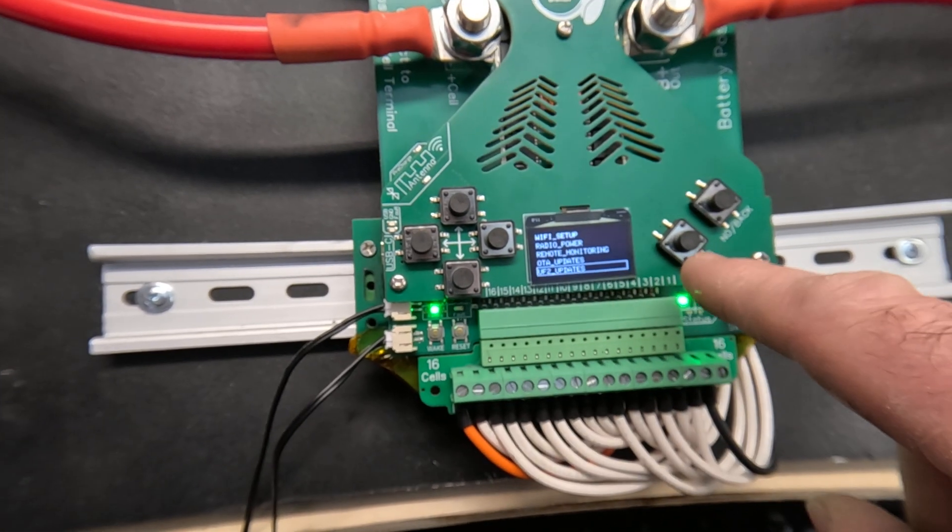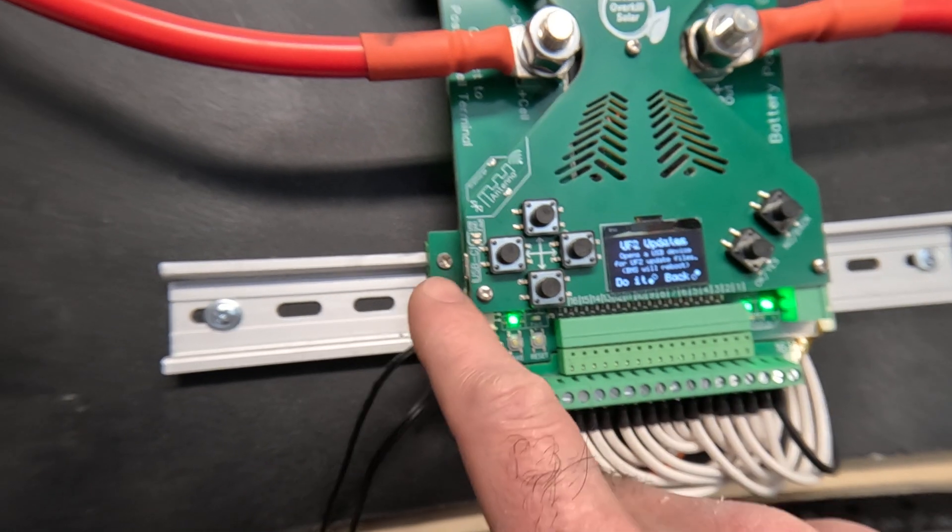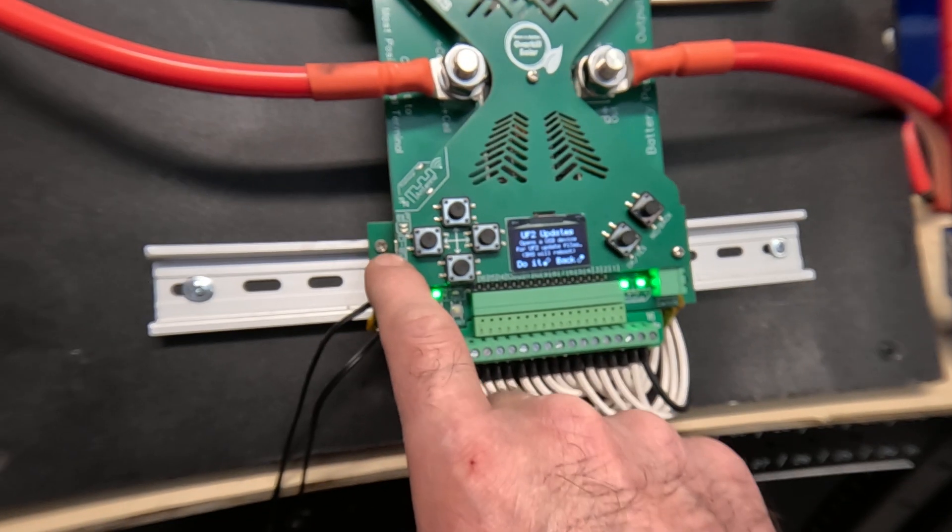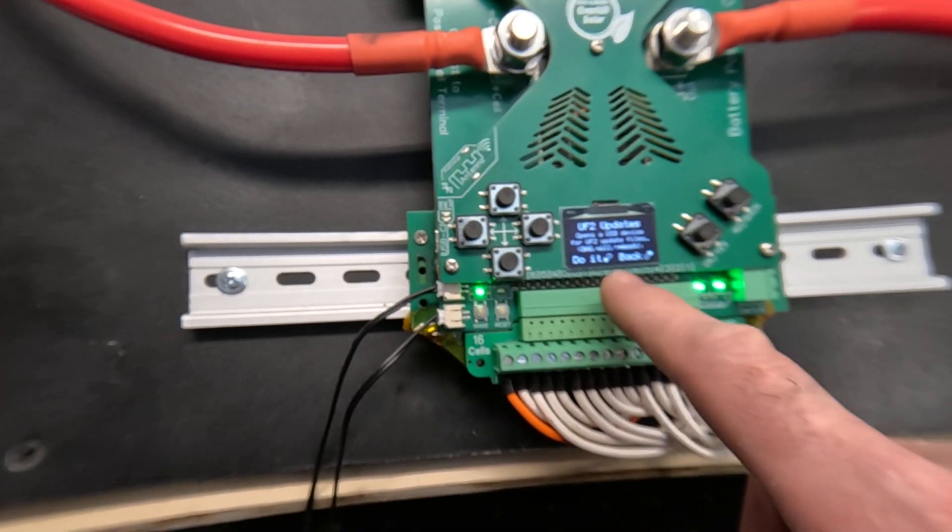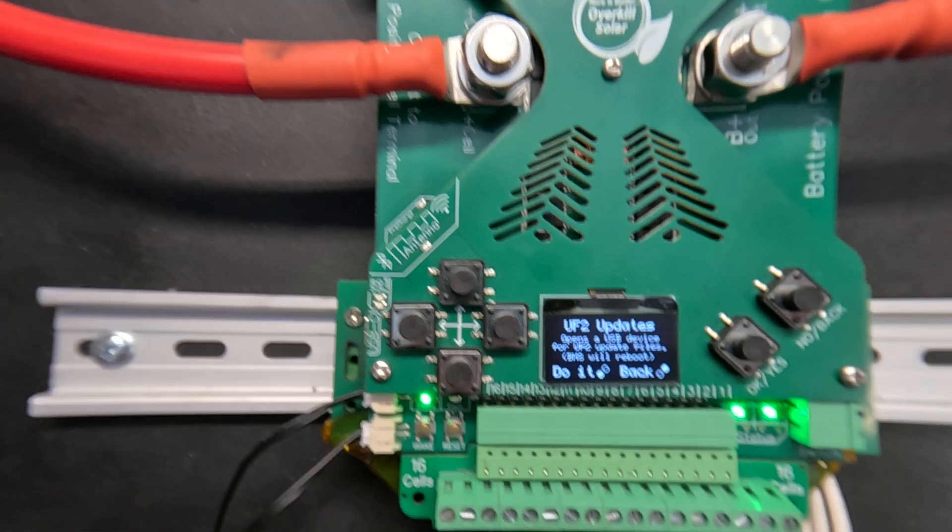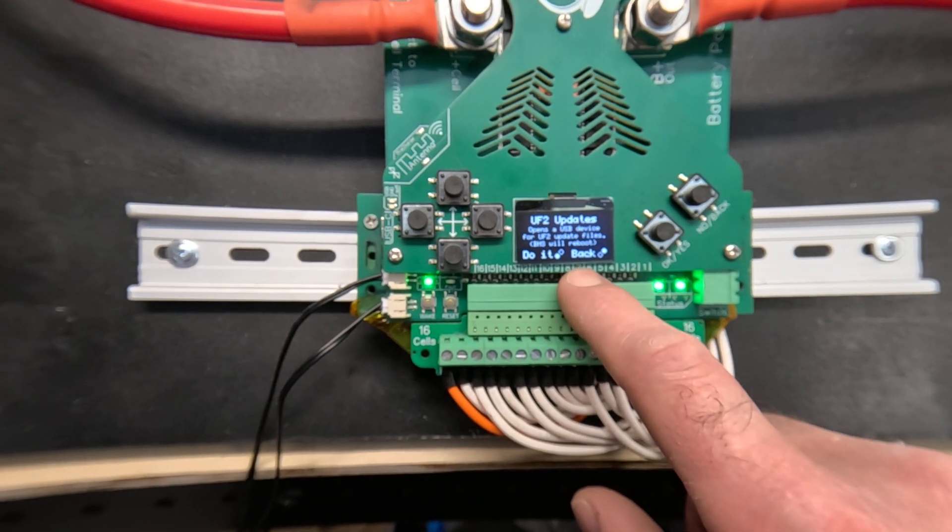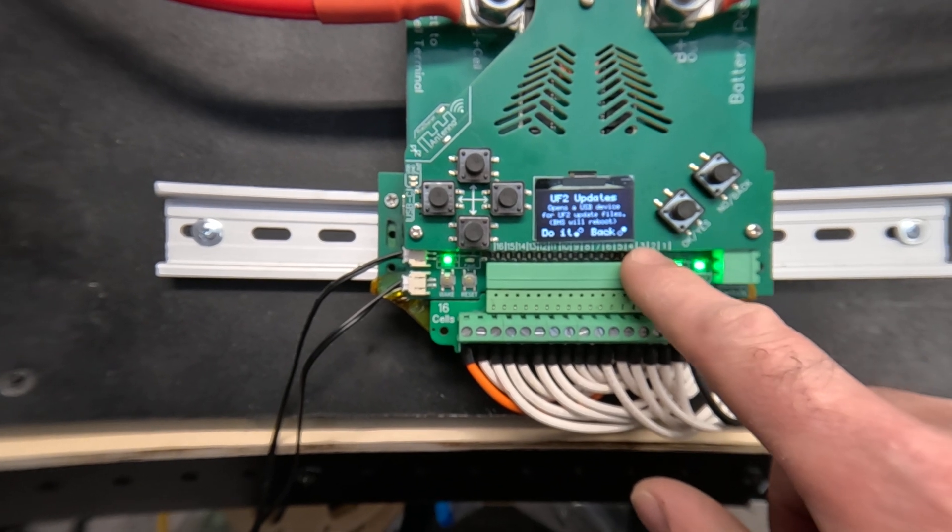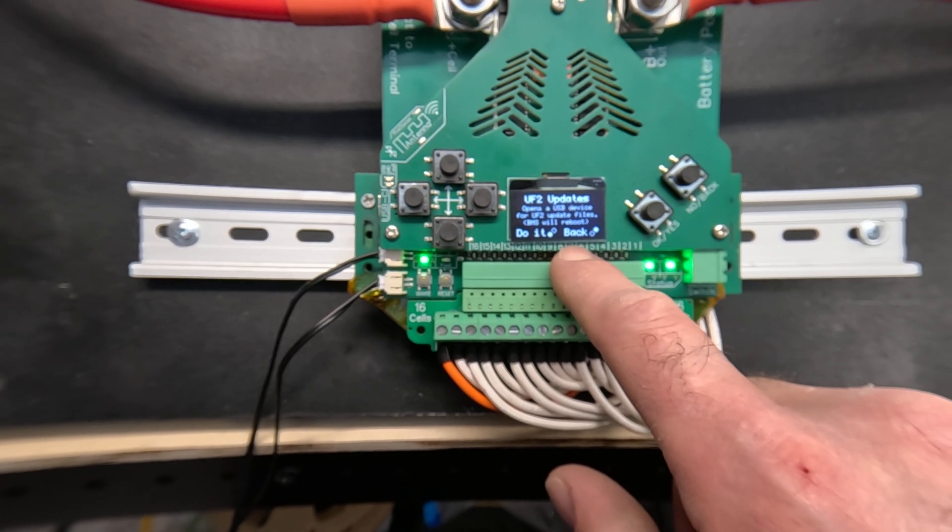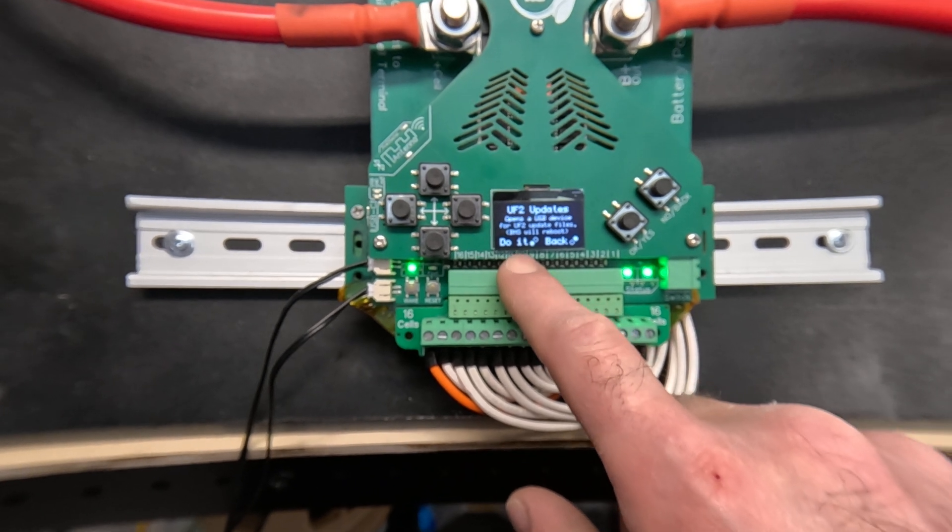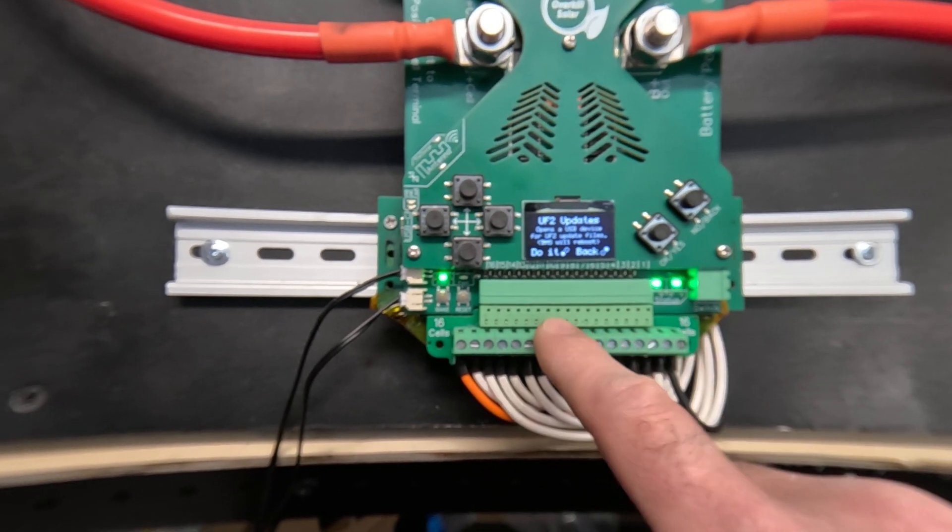You can also enter the UF2 update mode. This is how you update via the USB. So you would connect this to your PC and download the UF2 format firmware or update. And then you just drag and drop it into the mass storage device. When you click OK here this will reboot and it'll present a mass storage device on the PC. And when you drop the update file in then the BMS will execute it and restart.